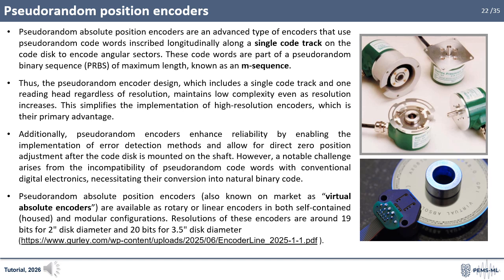pseudorandom encoders enhance reliability by enabling the implementation of error detection methods and allow for direct zero-position adjustment after the code disk is mounted on the shaft. However, a notable challenge arises from the incompatibility of pseudorandom code words with conventional digital electronics, necessitating their conversion into natural binary code. Pseudorandom absolute position encoders, also known on the market as virtual absolute encoders, are available as rotary or linear encoders in both self-contained and modular configurations.